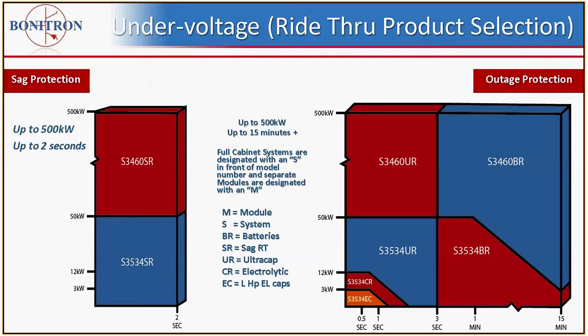So once again, on the left we have sag protection, which is a single unit that can be used to correct for sags up to 60% for 2 seconds. And also you're going to use a kilowatt rating, and the kilowatt rating corresponds to whatever power the motor requires during the ride-through process. So in other words, we size to the actual motor ratings of whatever motor is tied to the VFD that's tied to the ride-through.